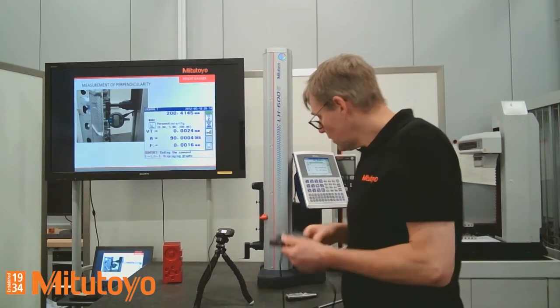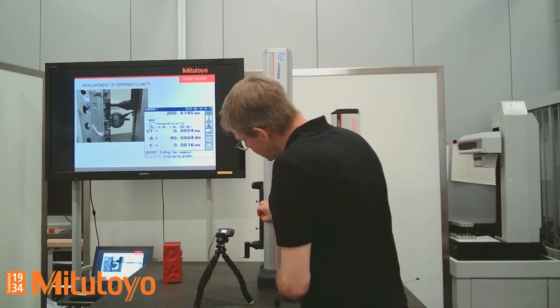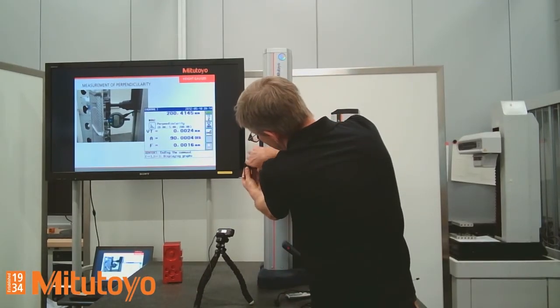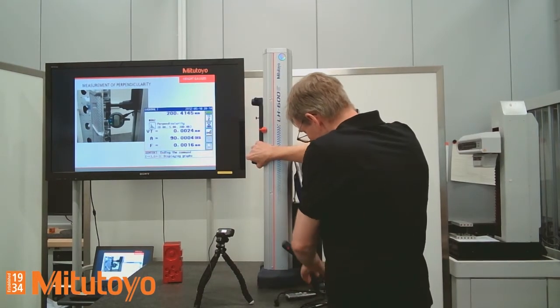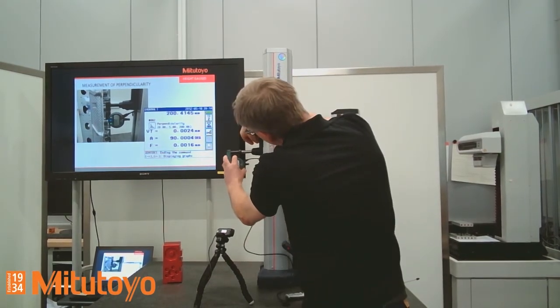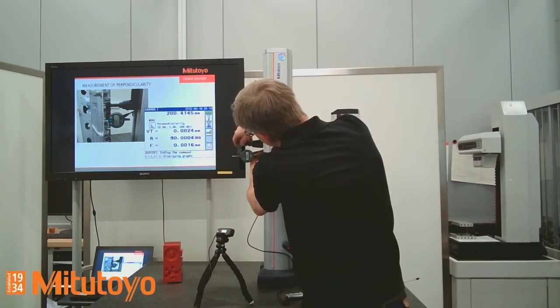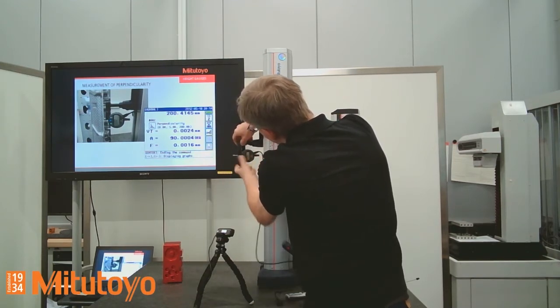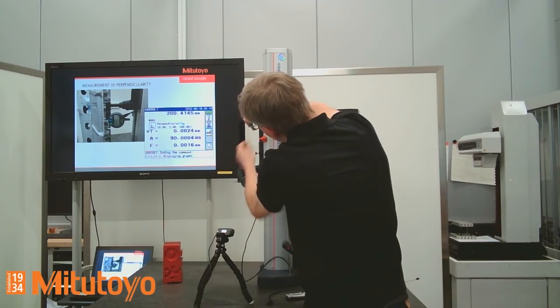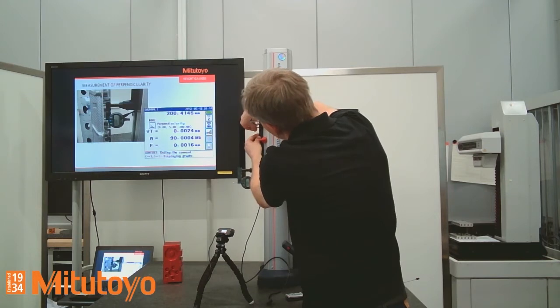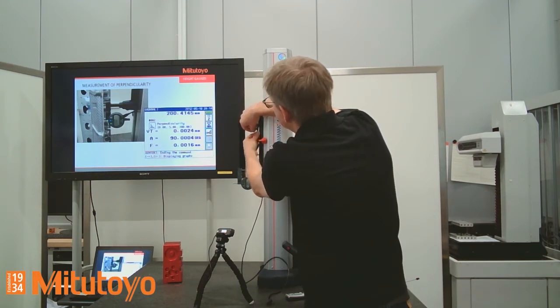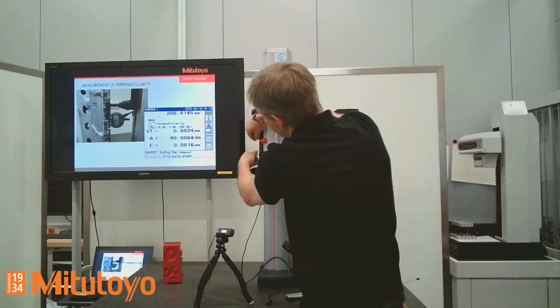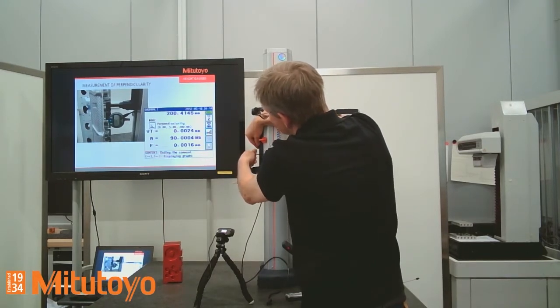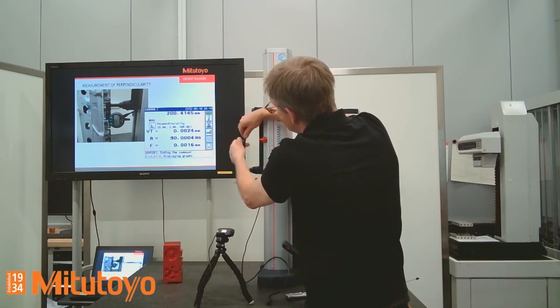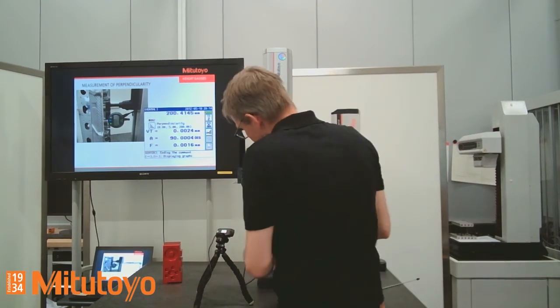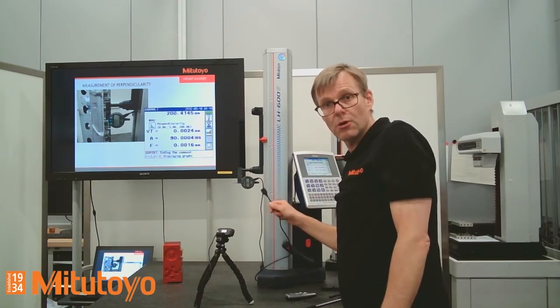Yeah. So I will put this one here inside instead of the standard probe. You can see here, I will take it out. I will put this one inside here, like this. And I have to remove some weights, because altogether the holder with the integrated indicator is a heavy weight. So we have to remove the counterbalance weights. This one here. And I have to connect this one here to the controller box of the linear height.